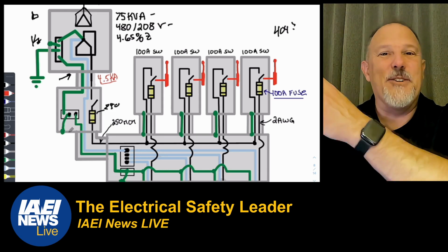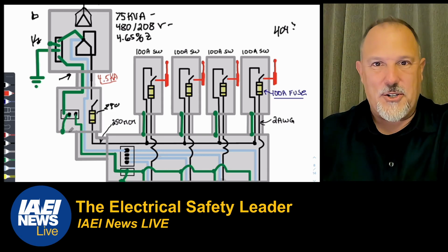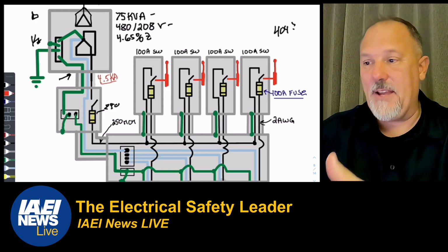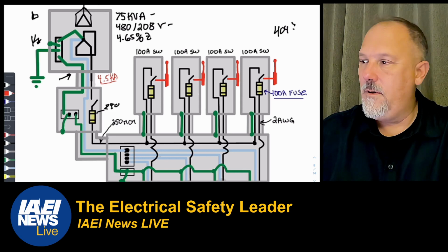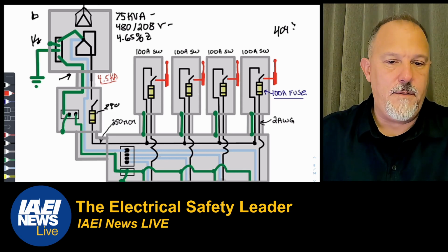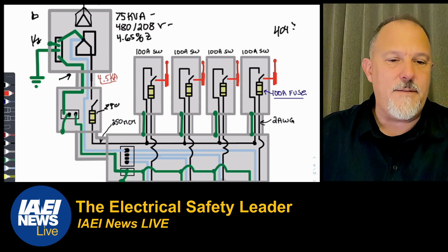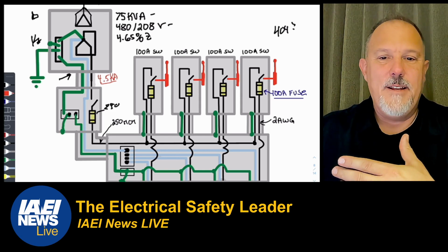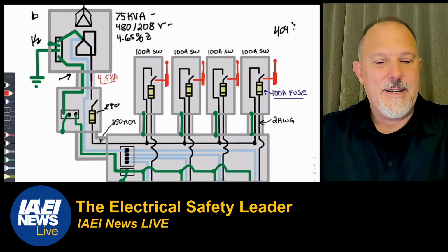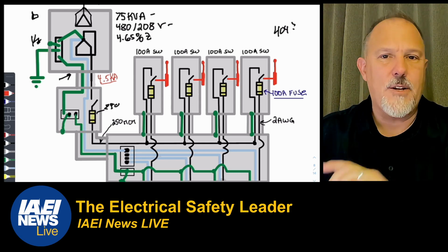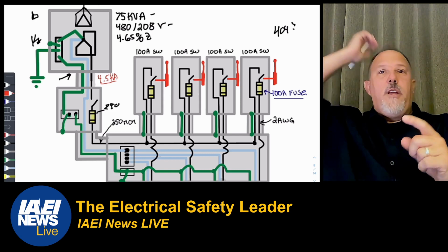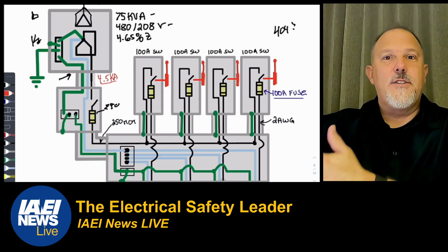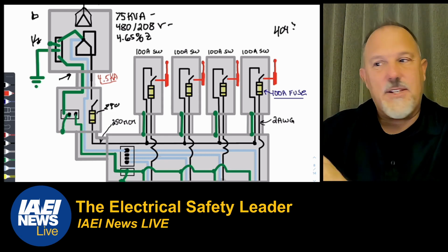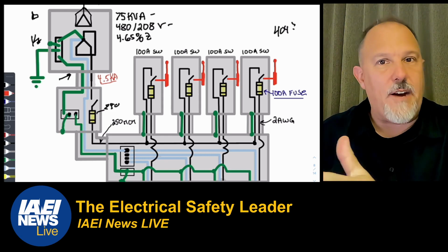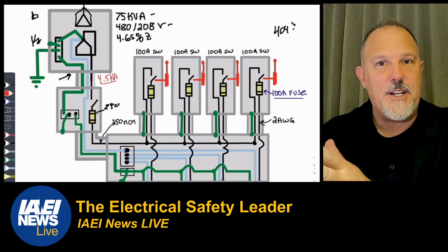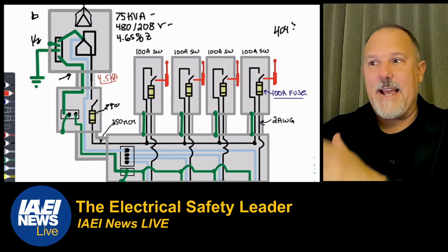All right. So you're into 110.10, helping somebody understand the short circuit current rating. Marking of available fault currents on panel boards, etc. That's in 408. No, not 408. See, for some reason, I don't know how you all are, but panel boards, switchboards, 408. Yeah, it is 408, and I don't know why I questioned myself. So 408 tells you to mark the available fault currents, right? Do you see how this example can branch off into many different areas for teaching and helping people understand how the National Electrical Code relates?